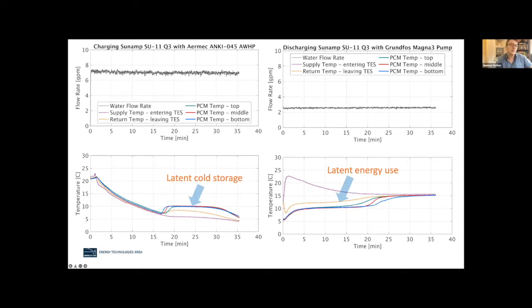Supercooling is an issue where, if you look at the plot on the left, this shows charging a Sunamp battery. As you can see, the temperature of the fluid goes down and down as it passes through the battery, and it actually has to dip below the 11 degree C temperature that the battery should be freezing at in order to trigger nucleation, the freezing of this thermal battery. This is a challenge for phase change materials in general.